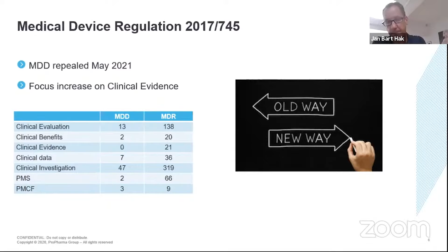And we need a bit more than that. So on one hand, we have the regulatory requirements. In your documentation, in order to prove that your device is doing what it is supposed to do and that it is safe, so the regulatory data, you also have to have a couple of other things in place in your organization. If you are the manufacturer of a device, and that means also the party that designs it, you have to have a quality management system in place that takes care of risk management, clinical evaluation, and, in the G line, you see I've underlined design and development, and last but not least, setting up, implementation and maintenance of post-market surveillance activities.